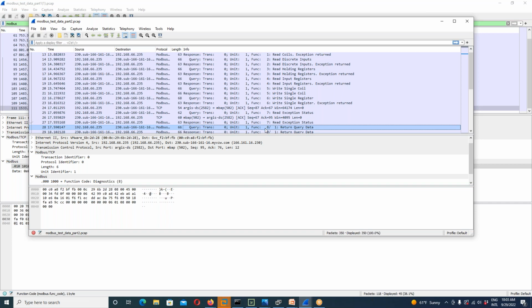Voltage says Rapid SCADA would have a different packet naming protocol. Yes, once again, there's that proprietary nature that everybody's using, so it's likely to be slightly different depending upon what environment they're using, since Rapid SCADA can be used in multiple environments. It's also true that Schneider Electric has what they call Modbus Plus - they use the same basic function codes, but add additional function codes that only work on their systems. Hopefully that answered those questions.